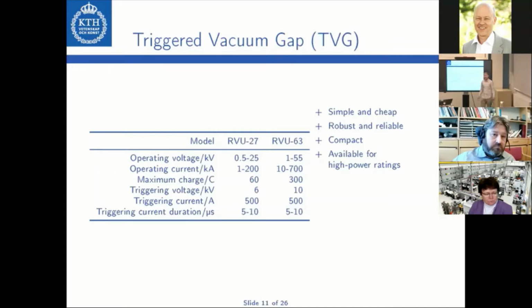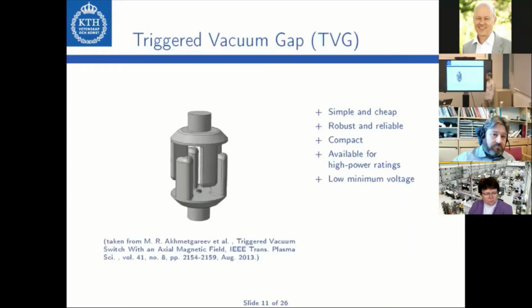And also, considering the high voltages, the number of series connected components in the commutation path is reduced. Another plus of the triggered vacuum gap in particular is the minimum voltage required, which is very low compared to other similar switches. A practical aspect is that no cooling system is needed. The disadvantage is that the characteristics of the triggered vacuum gap in DC circuit breaker applications are still unknown. Only few manufacturers sell such triggered vacuum gaps nowadays. This is because triggered vacuum gaps are only used in niche applications. However, they are so simple that manufacturing could be increased at any time if there should be a sufficient demand.